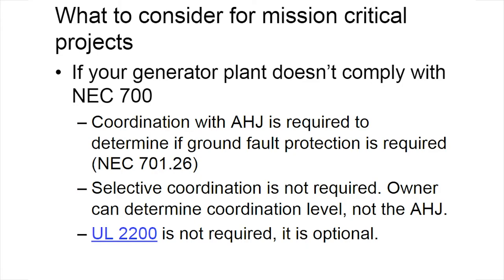It's important to say that when you're in 700, and I believe it was even one of the questions, about ground fault protection, you need to coordinate your ground fault protection. If you use ground fault protection, you have to make sure that it is selectively coordinated. I mean, you start with your 1200 and then you go up to 1800 and so on to make sure that it is coordinated. But if you're not using 700, this coordination is not required. So sometimes you don't even have to have ground fault.